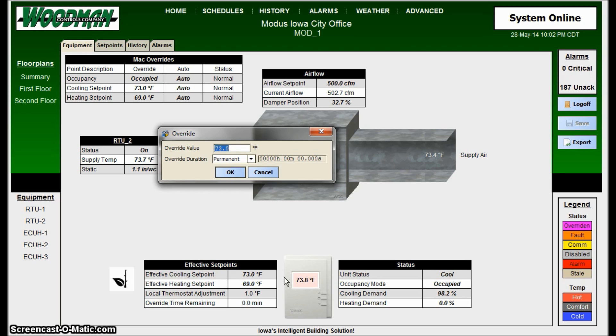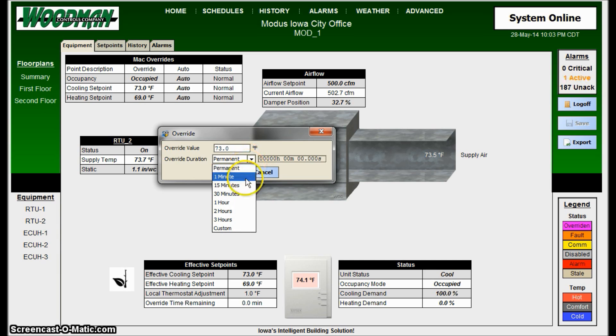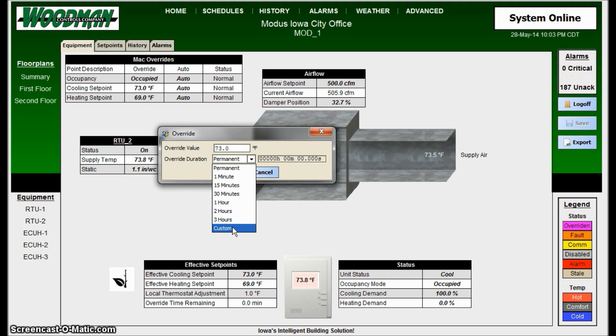One thing that tends to happen is people use this as a permanent override, which I wouldn't suggest, because once it's overridden it will never go out of it — and that can be a problem with fans and fan status. Get in the habit of picking a time for the override. I'm going to pick one minute, but you could pick a custom duration: multiple hours, days, weeks — for the whole summer, for example. When that time limit expires, the unit will go back into automatic operation.